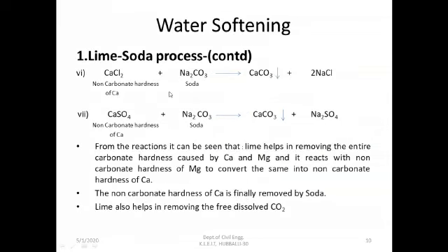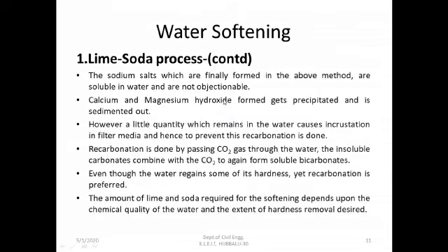And when soda ash is added, the non-carbonate hardness of calcium in the form of calcium chloride and calcium sulfate reacts with the soda ash to form calcium carbonate, which can be sedimented out. So this is how the lime soda process works. Now, the sodium salts which are finally formed in the above method are soluble in water and are not objectionable.